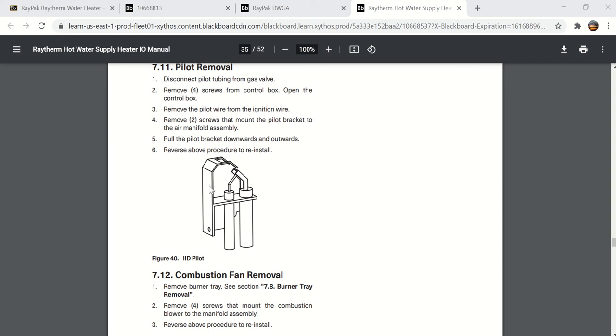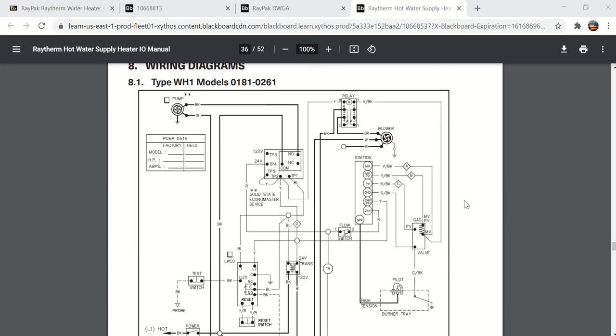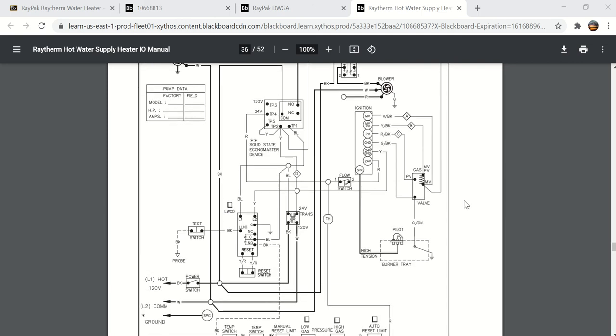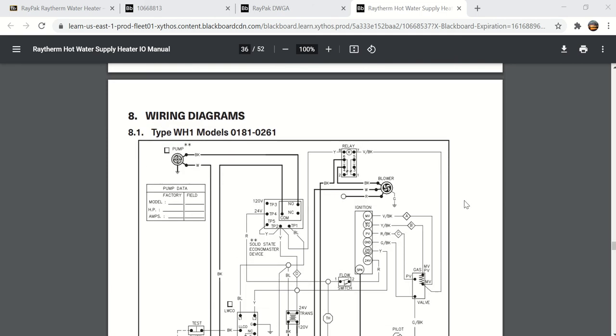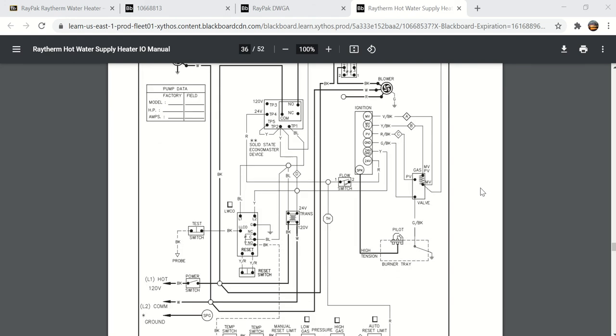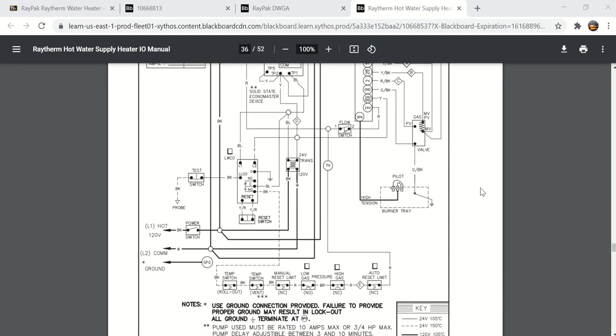up and hit this shield right here, and that's kind of a grounding shield. But this probe right here that sparks and lights the gas is also the sensor. So it's a combination spark and sensor all in one. You'll see down here on some of these drawings, now I did not use the drawing from this manual. The drawing I had was from an older manual. I couldn't find it online, but this one's going to be a little bit different.